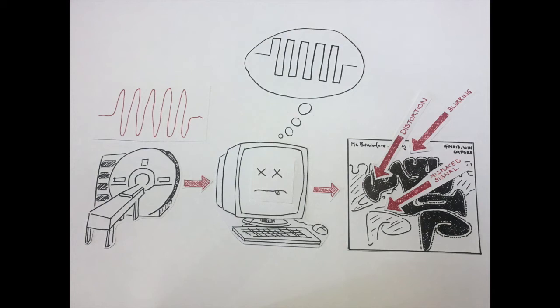Why is this happening? This is because the gradient took a different path to what it was supposed to take, but the image reconstruction computer does not know this. It thinks the gradient took the perfect path.